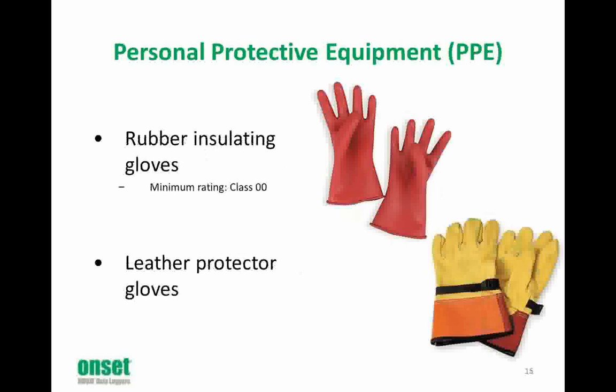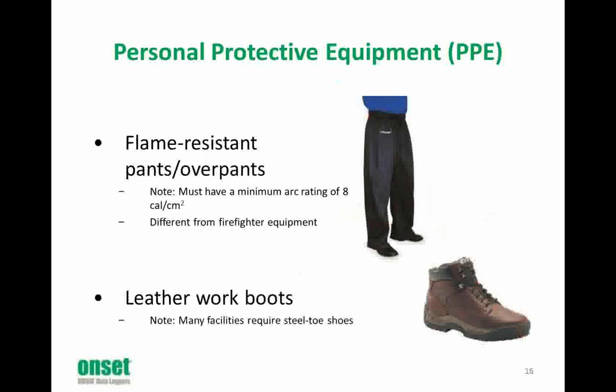We wear rubber insulating gloves. We want to make sure that they're class 00, with leather protector gloves, so during an arc blast the rubber will not melt. This will also help protect the rubber from abrasion. And then we must wear flame-resistant pants or overpants, again with the same arc rating of 8 calories per square centimeter, and then leather work boots. Many facilities that we visit will require steel toe shoes, and those are okay as well.